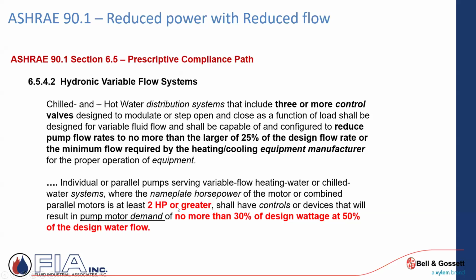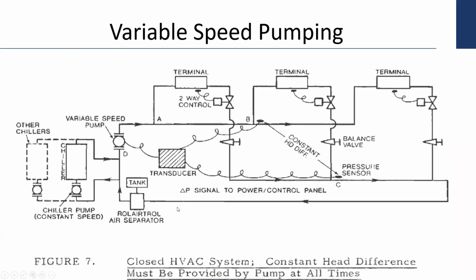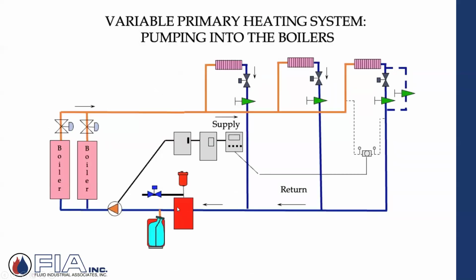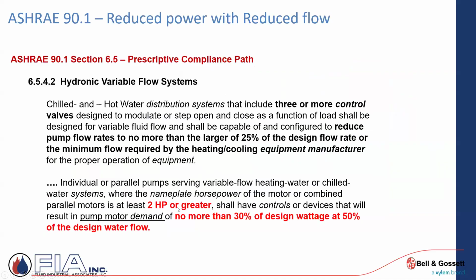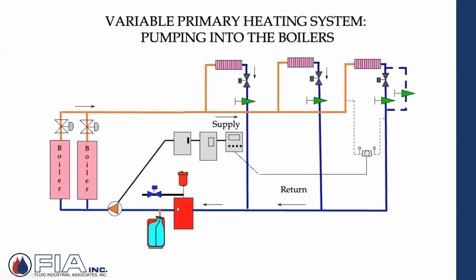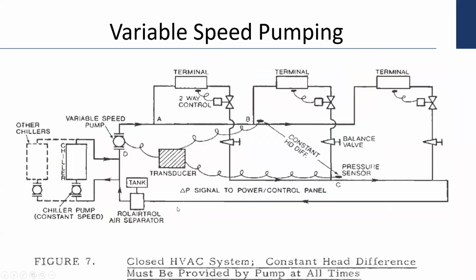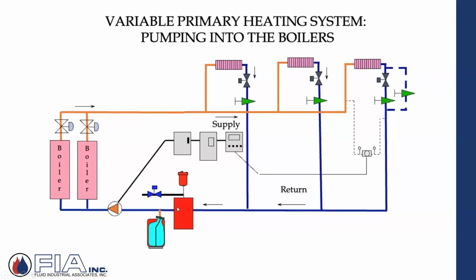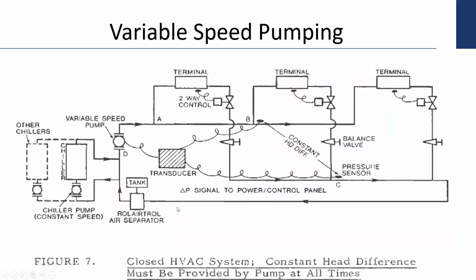So ASHRAE highly recommends, they're almost as restrictive, saying anything over 2 horsepower, you're going to introduce variable speed. You guys are doing variable speed all the time. This is what's going on. And obviously this is, again, maybe an older drawing, but potentially a little more current. What's the difference between these two pictures other than color? Variable primary, and we're still calling it variable speed, but how are the chillers connected to this distribution system?